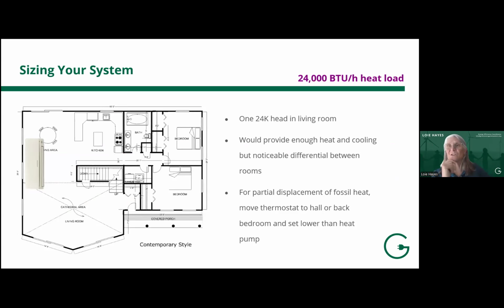I want to make a special note about sizing the equipment. This is very important. And some people have had problems with systems that were oversized. So to illustrate this question, we're going to posit this is a 2-bedroom unit. It's got cathedral ceilings in the living room. And a technician has calculated the heat load at 24,000 BTUs per hour. This is also called a 2-ton system. A ton of heating capacity is 12,000 BTUs per hour. And you could provide that 24,000 BTUs in a single unit that goes in your central living area. This would be like you have a home that has a wood stove, and that's your sole heating. That would mean the bedrooms are cooler in winter and warmer in summer. It may be fine if you have ceiling fans in these rooms.